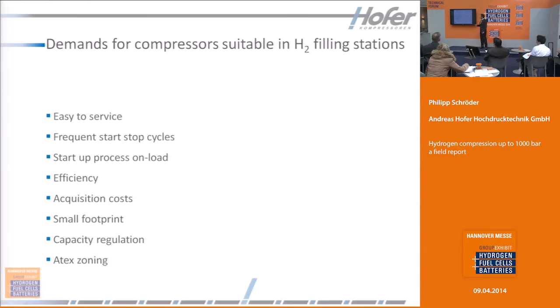There are some demands required by hydrogen filling stations. The first is it has to be easy to service. It needs to handle frequent start-stop cycles per day. The startup process must be on-load. Efficiency and acquisition costs are important. It needs a small footprint. Also very important is capacity regulation and ATEX zoning — the possibility to build it up in ATEX-classified areas.